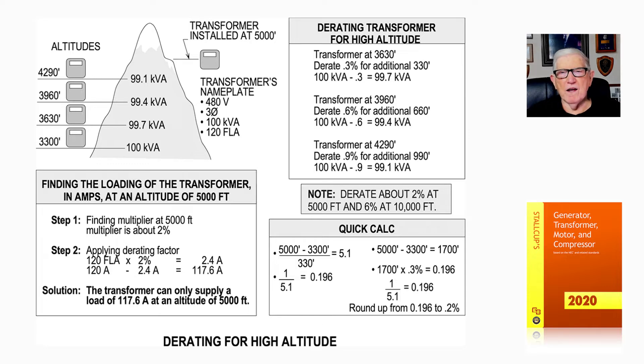Now to derate the transformer for high altitude, a transformer at 3,630 feet, derate .3% for additional 330 feet. So you take 100 kVA minus 0.3, and that would be 99.7 kVA. Then a transformer at 3,960 feet, you'd have .6% because it's 2 times 330. So 100 kVA minus 0.6 is 99.4.